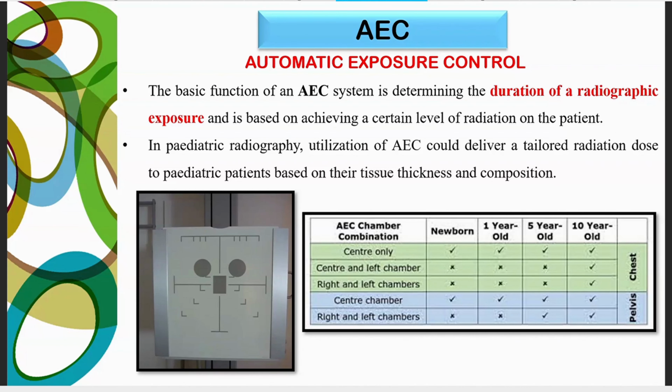And moving on to the AEC, that is automatic exposure control, which has been employed in our newer X-ray modalities. This will be helpful in determining the duration of radiographic exposure based on the patient build and contour. Pediatric radiography that utilizes the AEC delivers a tailored radiation dose to the pediatric patient. This shows the various chamber activation of AEC in the detector material used in the radiography area.